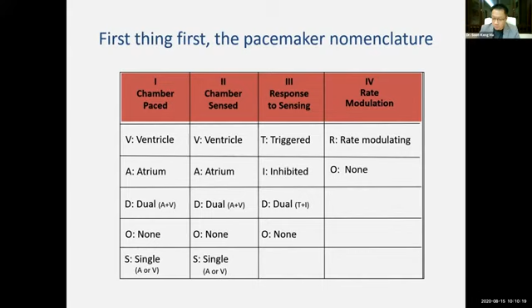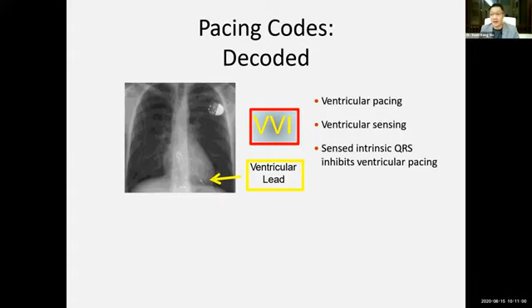Let's go to the most basic of all the pacemaking codes that we can have. We all started our career with this, understanding VVI. Now, V, the first alphabet, is which chamber has been paced. In this case, it is the ventricle. So it's a single lead system, single chamber system going to the ventricle. It paces in the ventricle and it senses in the ventricle. Now, what would I do as a pacemaker? If I sense an intrinsic cardiac electrical activity, I inhibit myself. I means I don't pace. I inhibit myself. Now, this is very easy to understand.